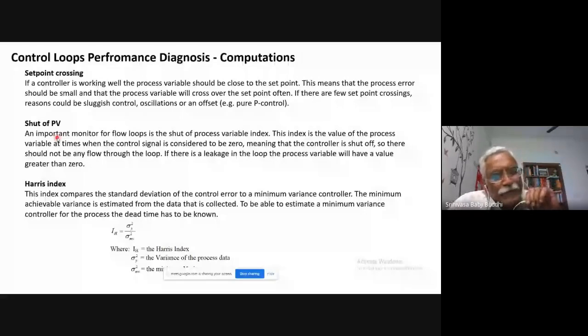But if you find that at shut off PV, when the control output is 0, there are process variable variations, like flow is varying and all that, it indicates that the valve is leaking. Okay.